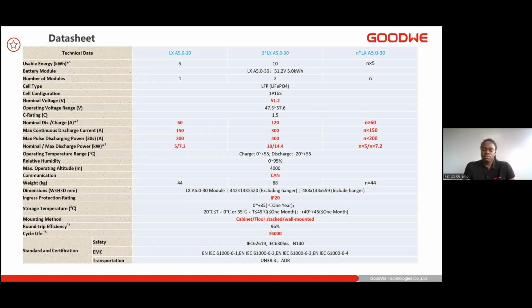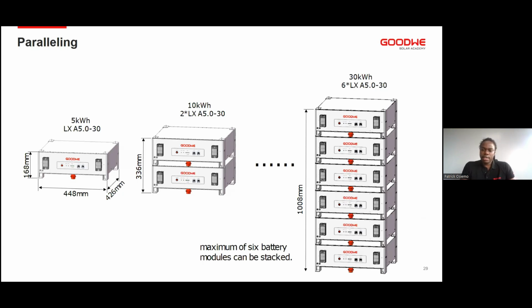This is how the battery can achieve a minimum of 5 kilowatts fully charged to a maximum of 7.2 kilowatts power discharge. All these states of operation are communicated securely to each battery BMS using the CAN protocol. And the battery is a high power battery, comfortable to reach a life cycle of 6,000 or more, depending on the usage. This slide displays how Lynx A can be stacked vertically. You do have a weight restriction of up to 6 pieces per stack, but the total you can do in a bank is up to 15 pieces.